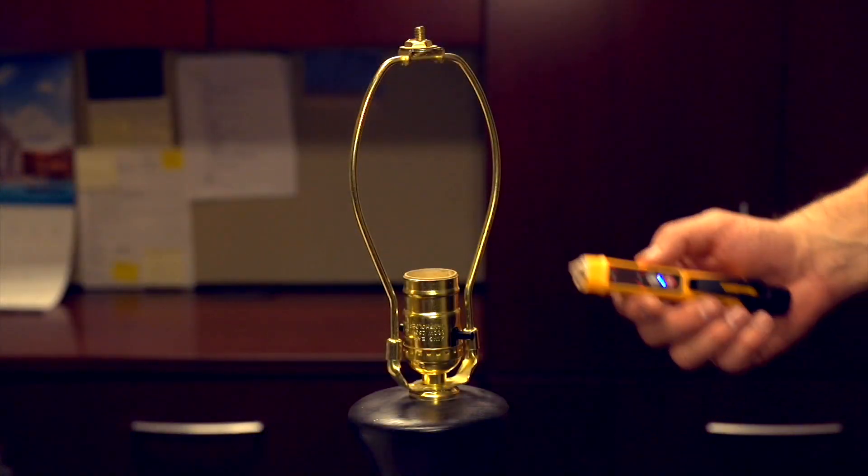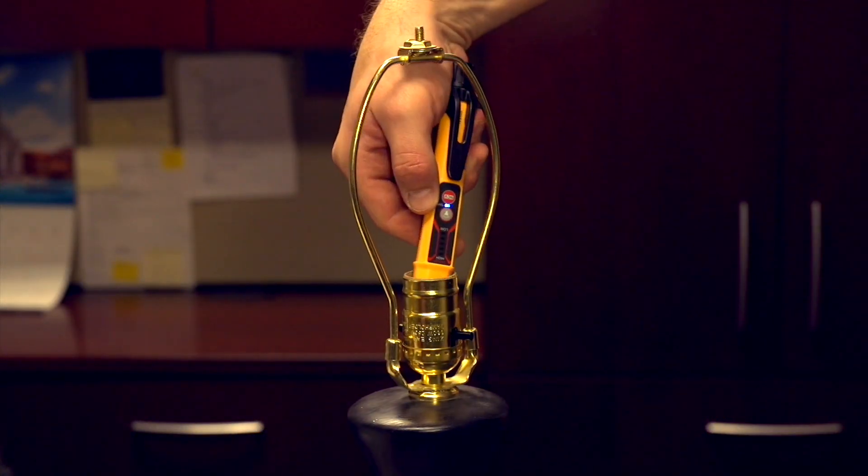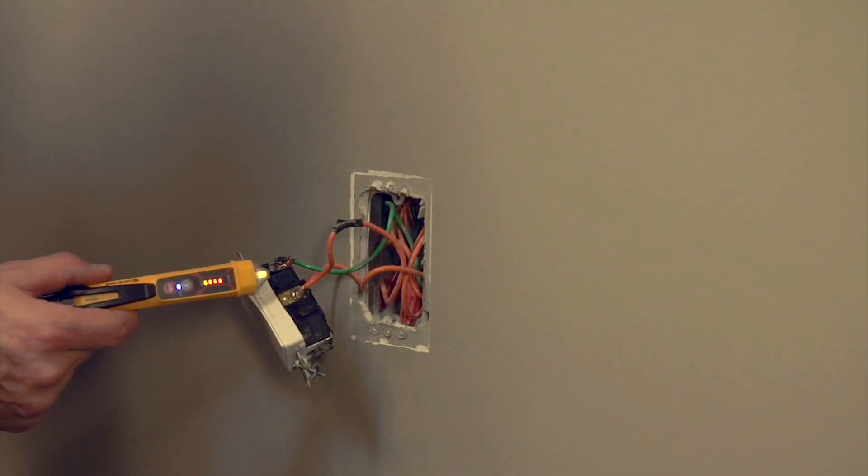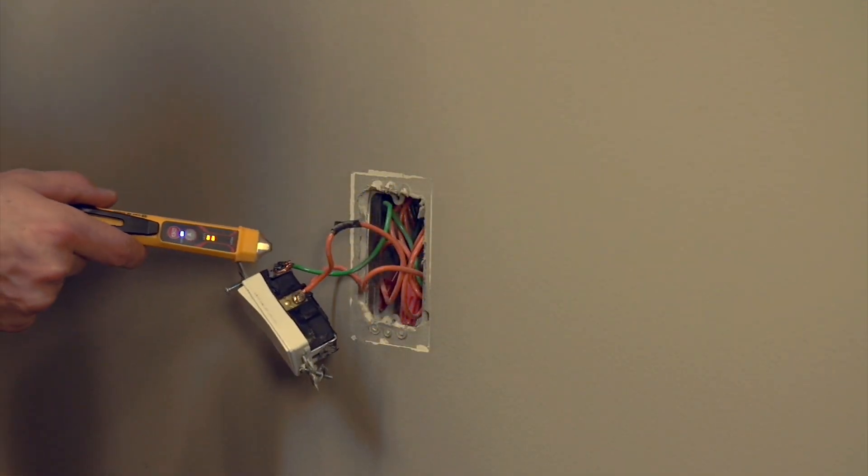Then test the unknown system and then finally repeat the test on the known live system. When the non-contact testers detect the presence of voltage, various models may provide continuous chirps or you may see a series of flashes or both to confirm the tester has detected voltage.